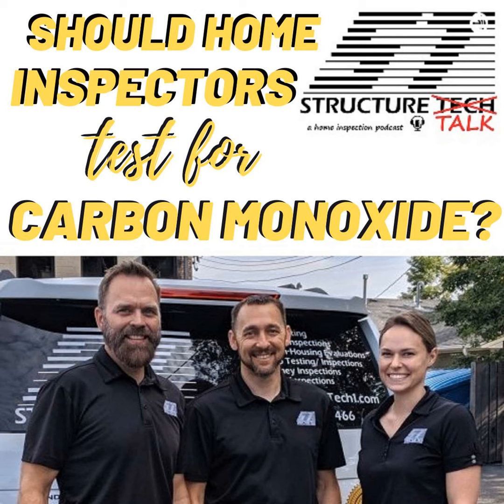This is because it is out of line here and it needs to be fixed. Yeah. And, Bill, while you're talking about equipment and we're talking about that magic number 400, I think it's important to note that a lot of equipment out there, a lot of CO testing devices don't actually take the right reading, because there's two numbers. There's the raw amount of CO in the flue gas, and then there's the air-free number.